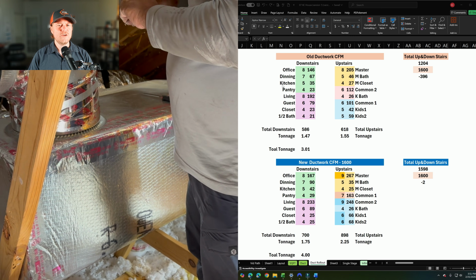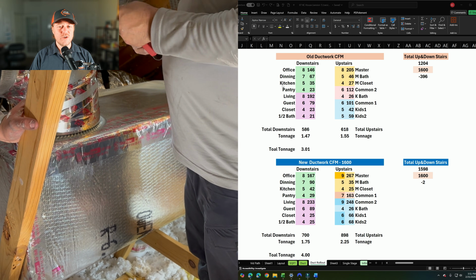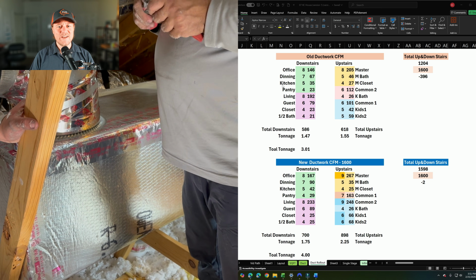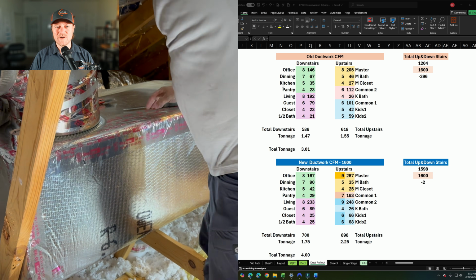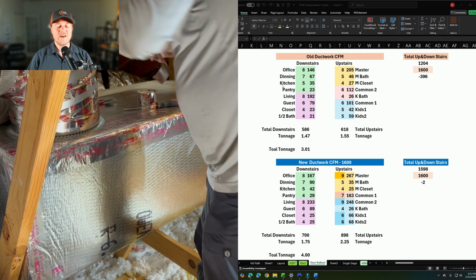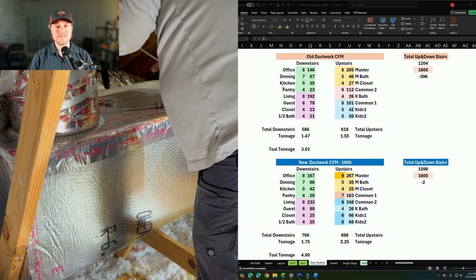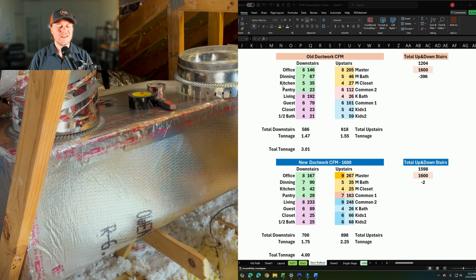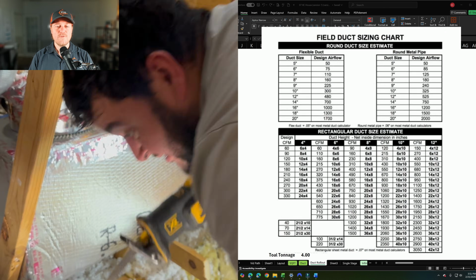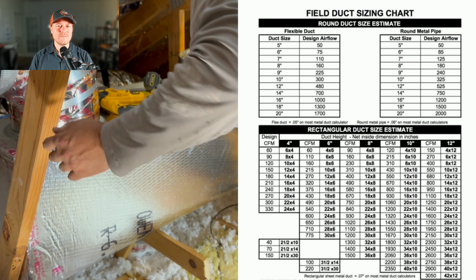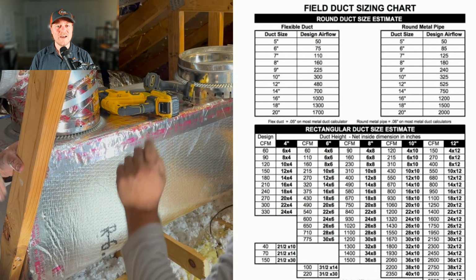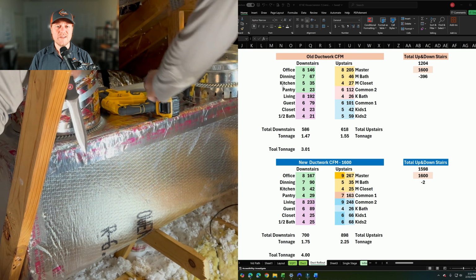The one thing that we do know that's 100% accurate is our delta is accurate. That means I added an additional ton of ductwork, and we're getting an additional ton of airflow. Now that that's out of the way, let's get back to our readings. There are a couple things here that I find pretty interesting. The first is it's kind of crazy how accurate this chart is that we use to design our ductwork. The second is the downstairs.